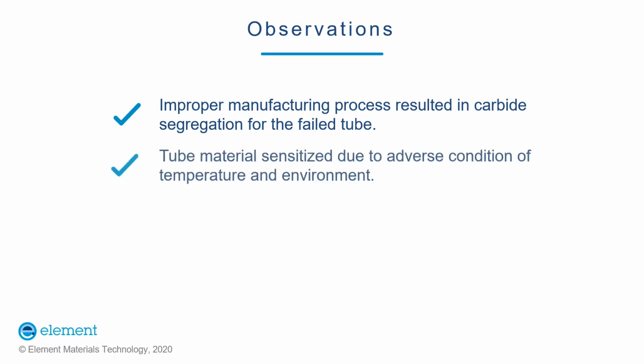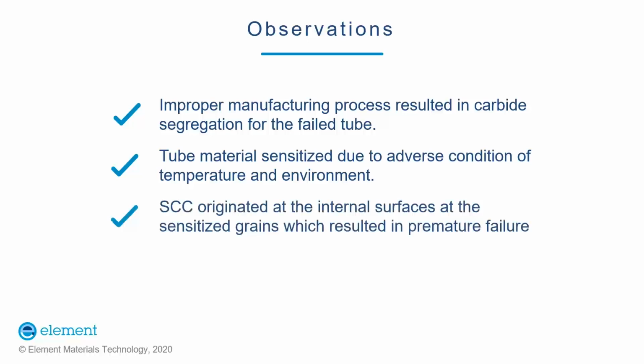Due to adverse environmental conditions, sensitization occurred even though the temperature was below 500 degrees centigrade. Sensitization followed by stress corrosion cracking can be attributed to the unwanted microstructure of the failed tube, which also explains why other tubes didn't fail and only one did.